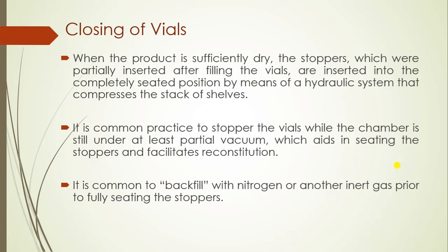After secondary drying is completed, the next stage is closing of the vial. When the product is sufficiently dry, the stoppers which are halfway closed or partially inserted into the vial are completely sealed by a hydraulic system that compresses the stack of the shelf, fully closing the halfway-inserted closures into the vials. It is common practice to stopper the vials while the chamber is still under at least partial vacuum, which aids in seating the stoppers. It is also common to backfill the product with an inert gas such as nitrogen or argon prior to fully setting the stoppers.